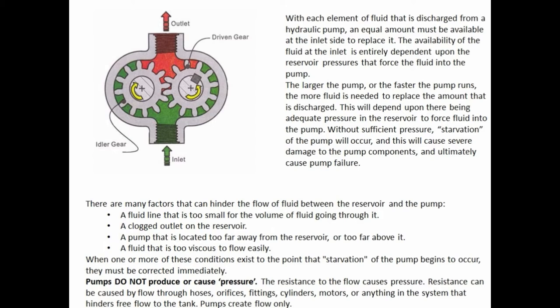Pump starvation will cause severe damage to pump components and ultimately pump failure. Many factors can hinder the flow of fluid between the reservoir and the pump: a fluid line that is too small, a clogged outlet on the reservoir, a pump located too far from or above the reservoir, or a fluid that is too viscous. When these conditions cause starvation, they must be corrected immediately. Pumps do not produce or cause pressure — resistance to flow causes pressure. Resistance can be caused by flow through hoses, orifices, fittings, cylinders, motors, or anything hindering free flow to the tank. Pumps create flow only.